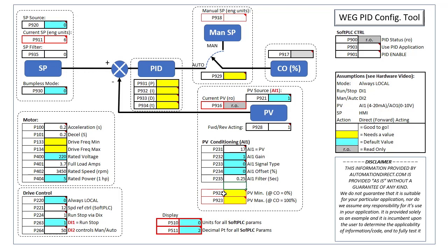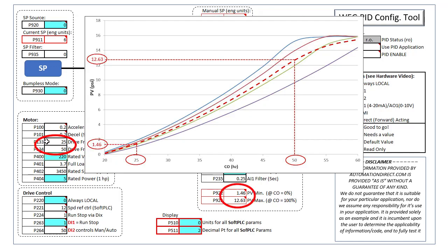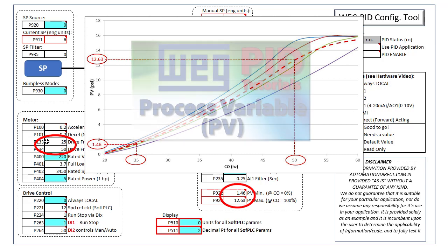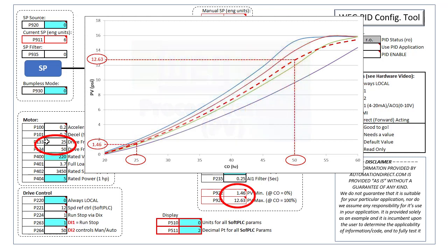Since the PID app expects the process variable in engineering units, we have to tell it how to convert the analog input to engineering units using PV-min and PV-max along with the min and max motor frequency. We derive those straight from the curves we created in the previous video. This is critical to your success and frankly this is the single most common thing I see folks screw up. So if you aren't real sure how to do that, then be sure to watch the process variable video where you will see how simple it is to get it right once you understand what these four parameters represent and how they work together to give you the best possible PID performance.